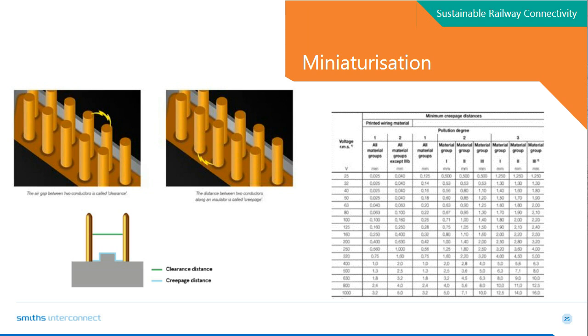Another very influential parameter is the material choice. Some materials have better electrical surface performance, typically called CTI, Comparative Tracking Index, which appears in the table by material group 1, 2, and 3. Depending on the pollution and the material choice, you can decrease or increase creepage distance. Our target is to choose good material to decrease creepage and clearance distance, increase density, and decrease connector size.